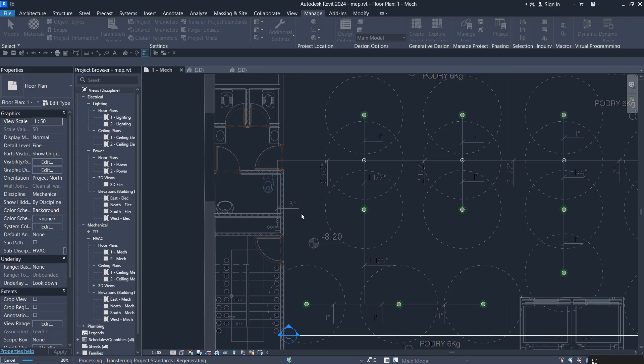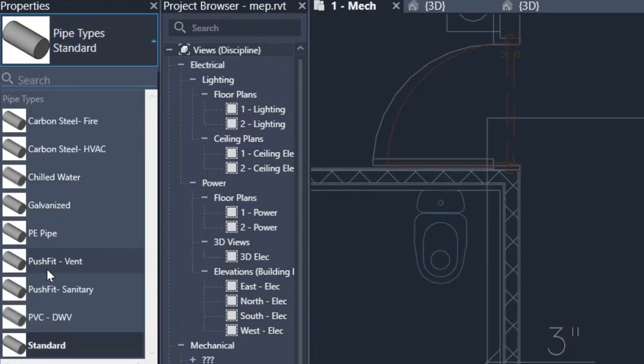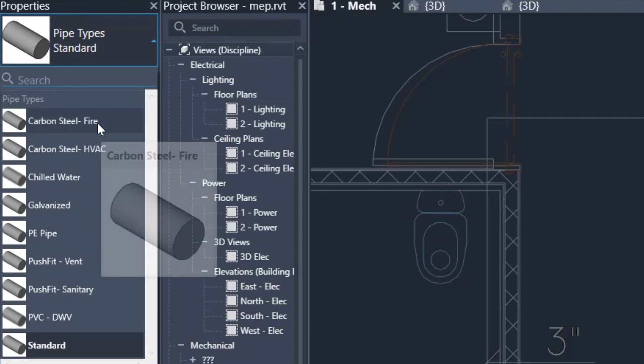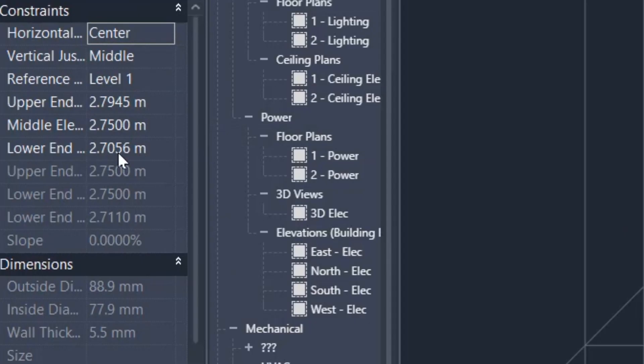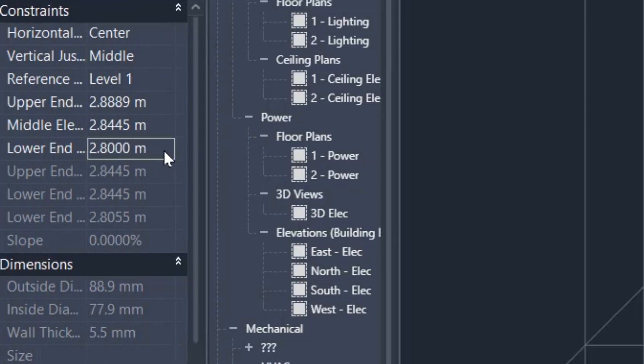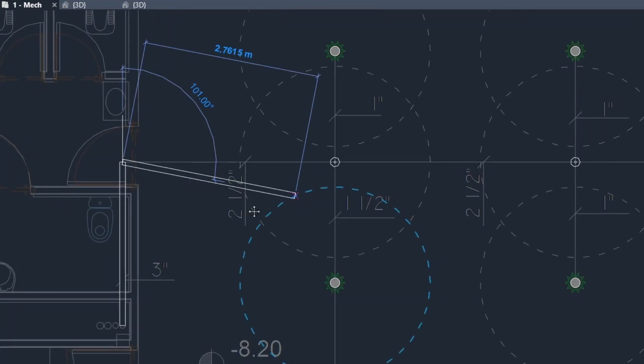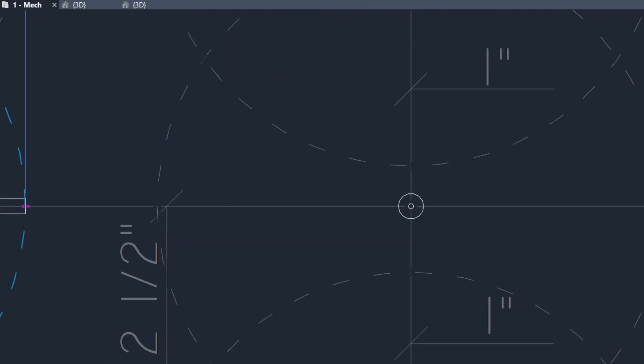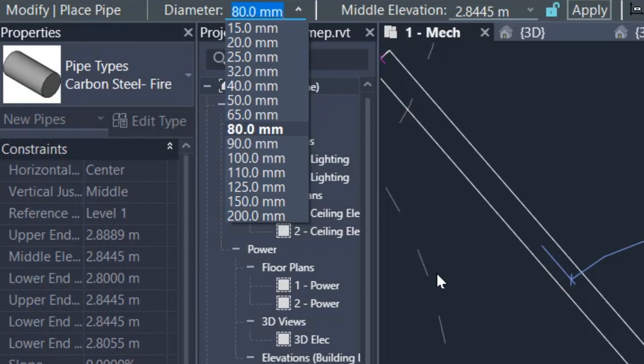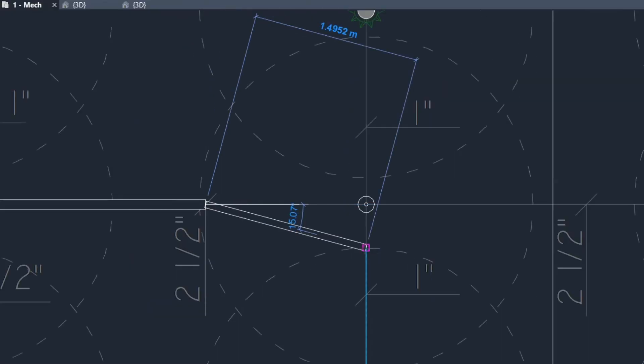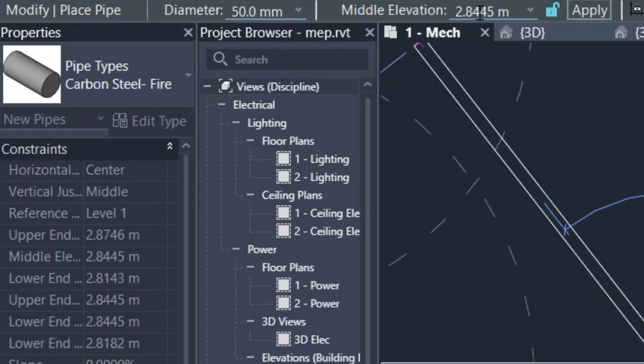Click Override when prompted, since it's better to override matching families from the source project. Now under Systems > Pipes you'll have a new type. We'll use carbon steel fire pipe. I'll use 80mm for the main pipe. Set the height for the lower part to 2.80 meters, then start drawing the main run. Then create a smaller pipe — I'm going to freehand this.